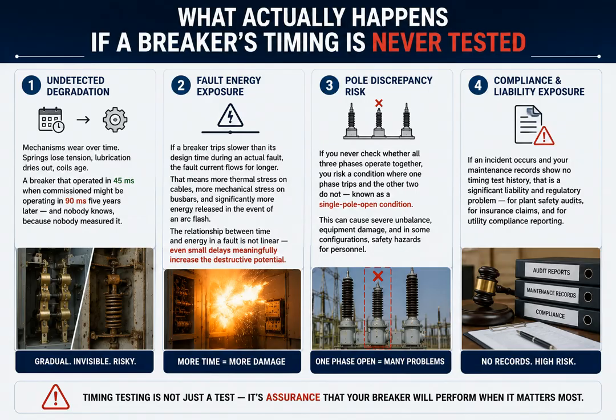What happens if a circuit breaker's timing is never tested? First, hidden degradation. Springs weaken, lubrication dries out, and trip coils age. The breaker may still operate but slower than intended. Second, higher fault energy. A delayed trip allows fault current to flow longer, increasing equipment damage and arc flash risk. Third, pole mismatch. If all poles don't operate together, it can cause system imbalance, equipment damage, and safety hazards. Finally, compliance risk. In short, a breaker may appear healthy, but without timing testing, you can't be sure it will operate correctly when it matters most.